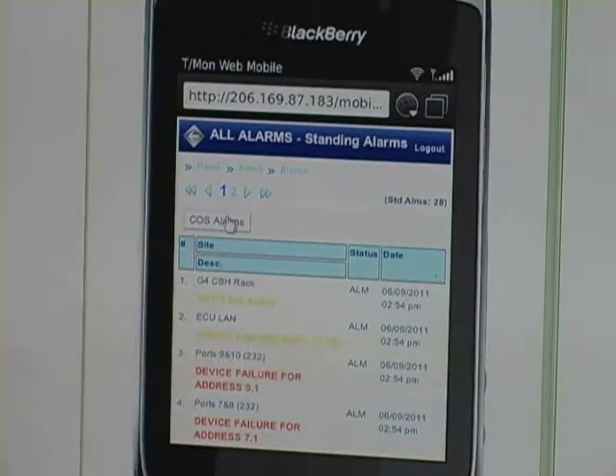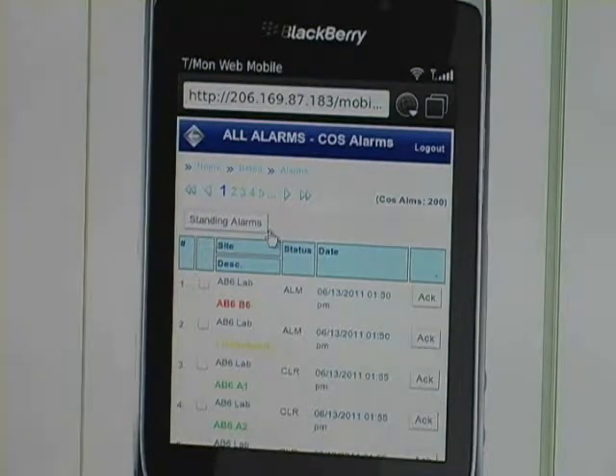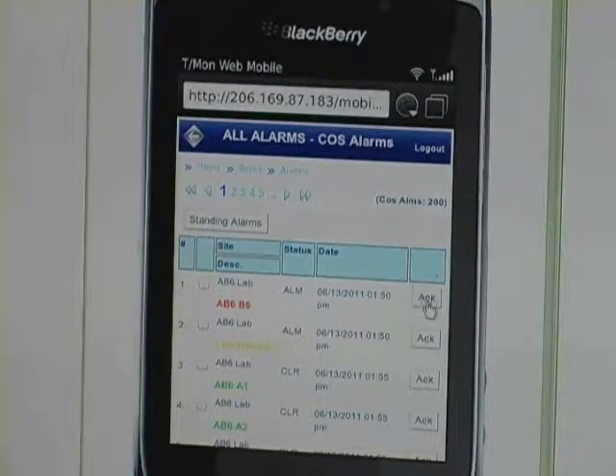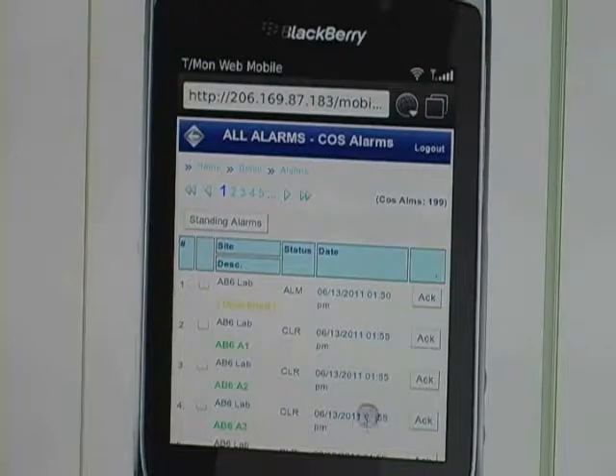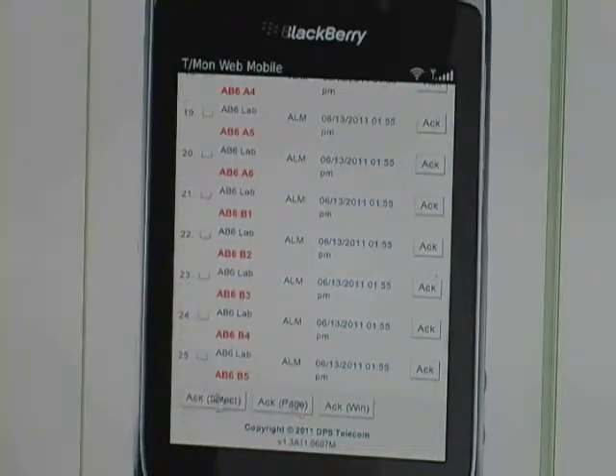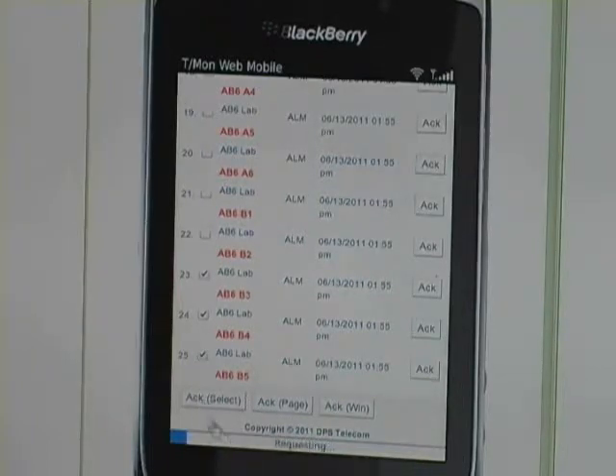You can also change over to COS alarms or change of state events. You'll see both alarms and clears, and you can acknowledge those so that other technicians on your team will know that you've handled that, because multiple people can be logged into the mobile web interface at the same time if you have a company where you have multiple technicians addressing problems simultaneously. You can scroll through the change of state events and use multi-acknowledgement options. If I select three alarms here and click Ack, I can acknowledge those — click Ack (Select), and now those have been acknowledged.